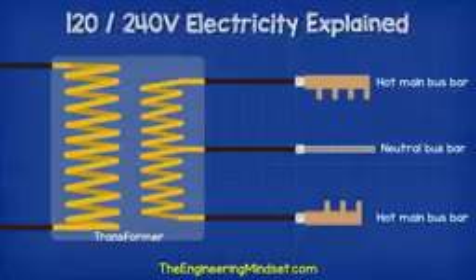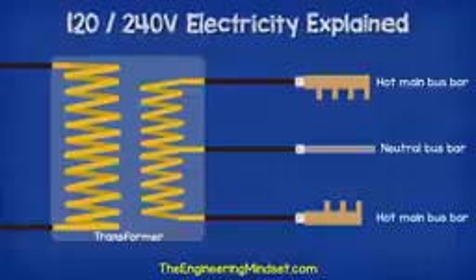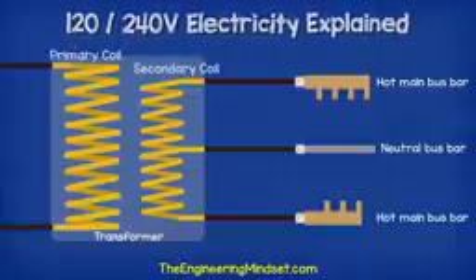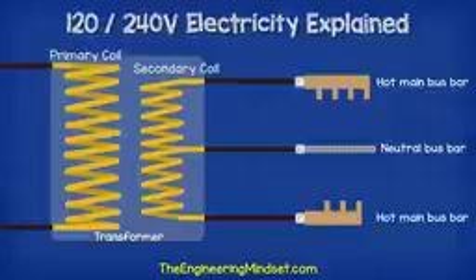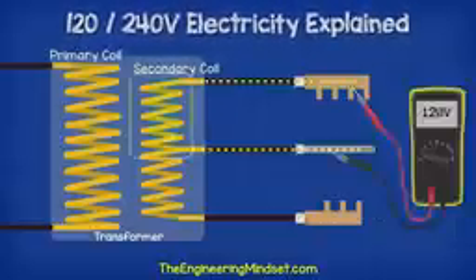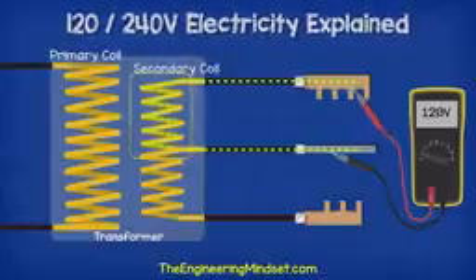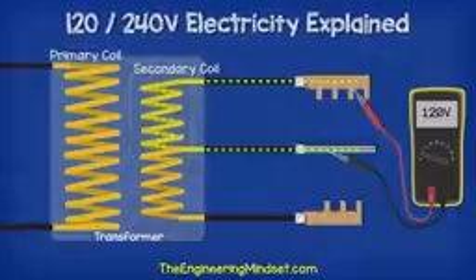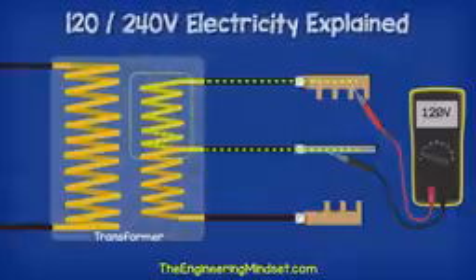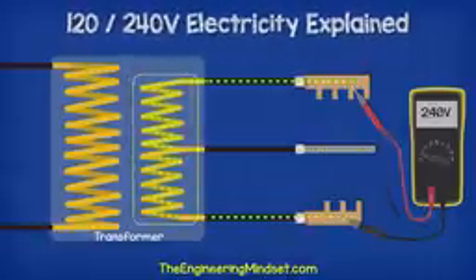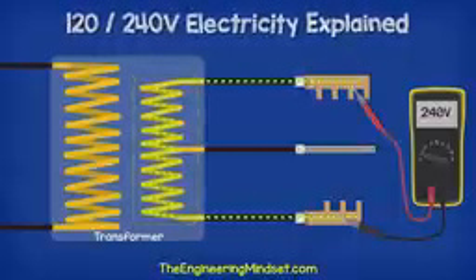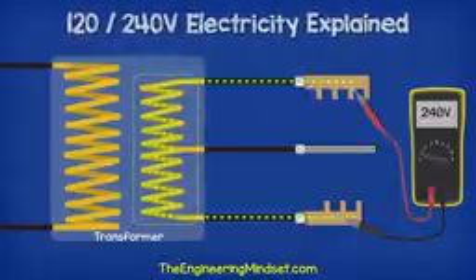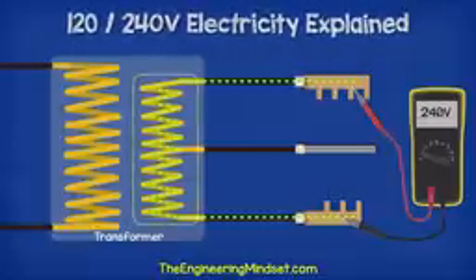So when we look at how the transformer is connected to the main panel, we have the two hot bus bars connected to either end of the secondary coil in the transformer, and then we take the neutral bus bar connected to the center of the secondary coil. So basically, when we connect across the bus bar and the neutral bar, we're only using half of the coil. So we are only picking up half the electrical voltage the transformer can provide, so that way we get 120 volts. When we connect to the two bus bars, we're connecting to the full length of the coil, so we're picking up the full voltage which the transformer can provide. Therefore, we get 240 volts.